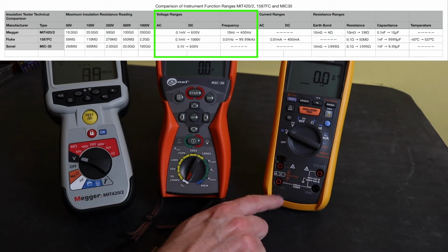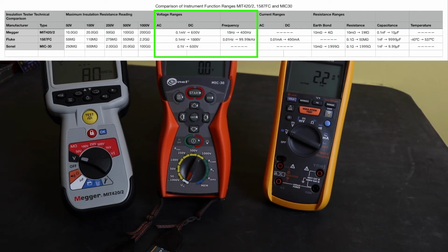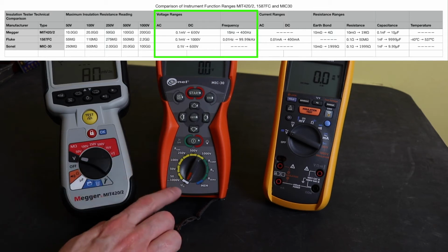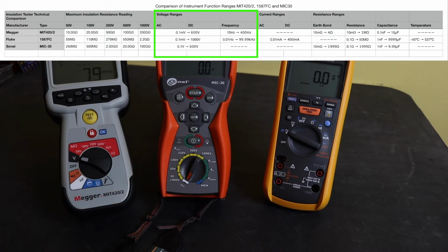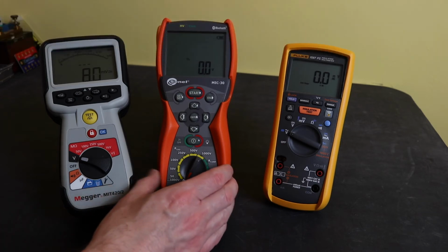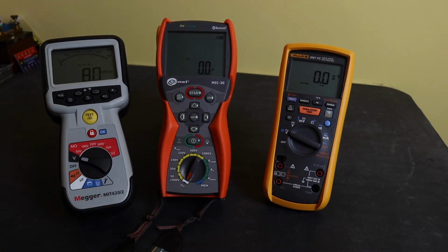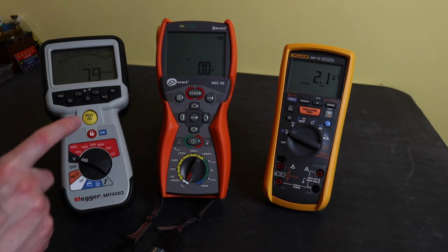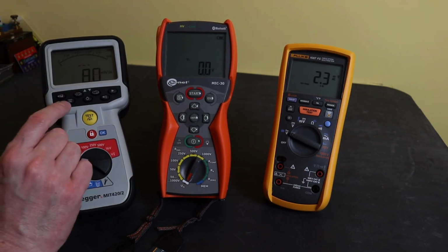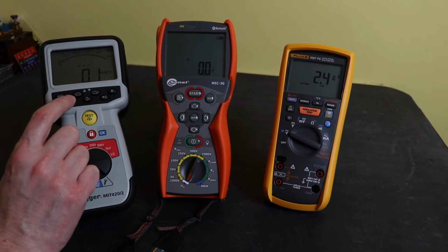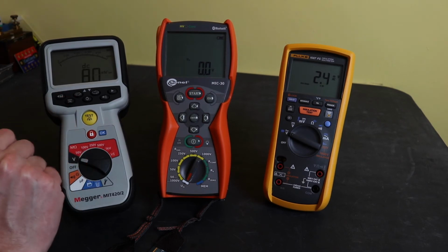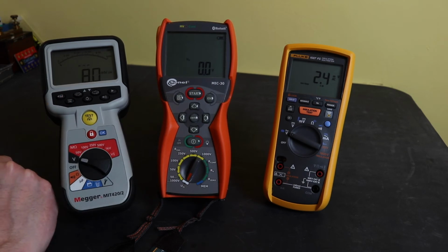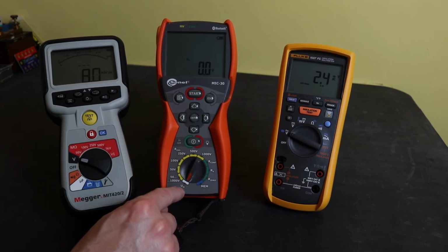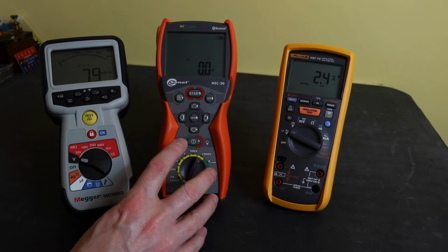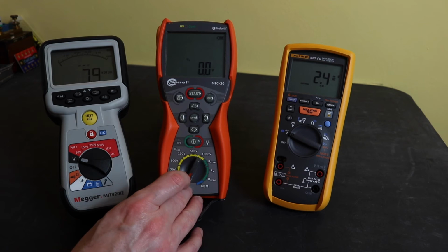The Fluke will measure from 0.1 millivolts up to 1000 volts, and the Sonel here will measure from 0.1 volt up to 600 volts, so it's got the narrowest range of voltage measurement. For the Megger, it defaults to an AC/DC mode. Using the TRMS button here, you can change that to an AC mode or a DC only mode, or back to the AC/DC mode. For the Sonel here, you only have an AC/DC mode that's automatic. You do not have the option to manually select AC or DC.